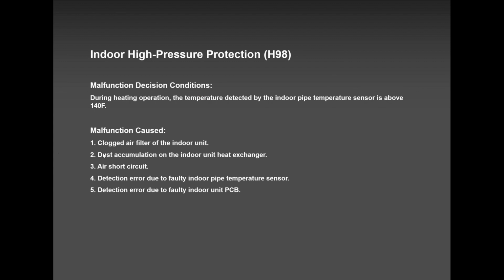But if there is no clogged air filter, no dust, no air short cycling, then definitely the capacity is not matching with the outdoor unit. The indoor units have been switched off and only one indoor unit is running. The unit will shut down on protection and it will come back on again and it will keep running. So not to worry much about the H98.